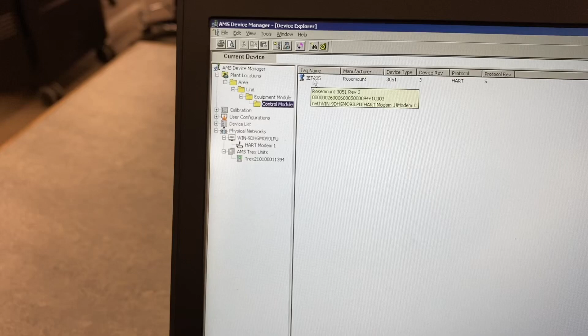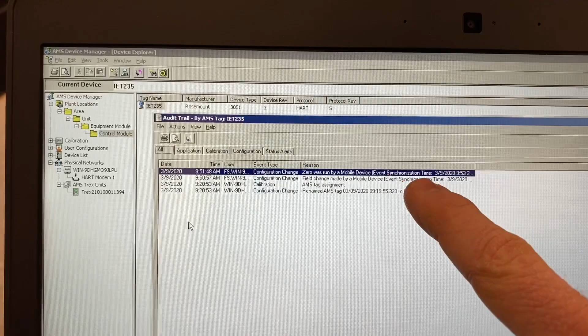And now I'm going to go over here to the device, make sure that we're selecting the one in control module here, right click on it and go to audit trail. And yes, right at the top here you can see zero was run by a mobile device, event synchronization time. So that time there corresponds to the time that we had over on our Trex unit, and you can see that zero was run. So the database here was not connected to the device. We used our Trex unit here to do the calibration. And it all gets logged.